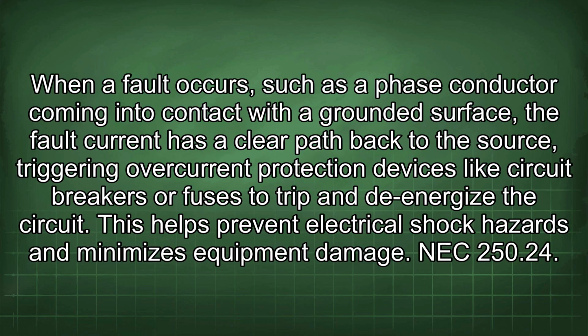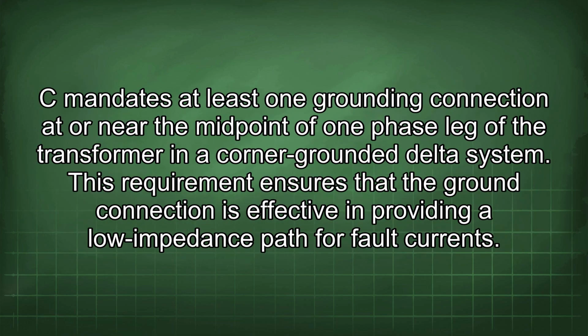When a fault occurs, such as a phase conductor coming into contact with a grounded surface, the fault current has a clear path back to the source, triggering overcurrent protection devices like circuit breakers or fuses to trip and de-energize the circuit. This helps prevent electrical shock hazards and minimizes equipment damage. NEC 250.24 C mandates at least one grounding connection at or near the midpoint of one phase leg of the transformer in a corner grounded delta system. This requirement ensures that the ground connection is effective in providing a low impedance path for fault currents.